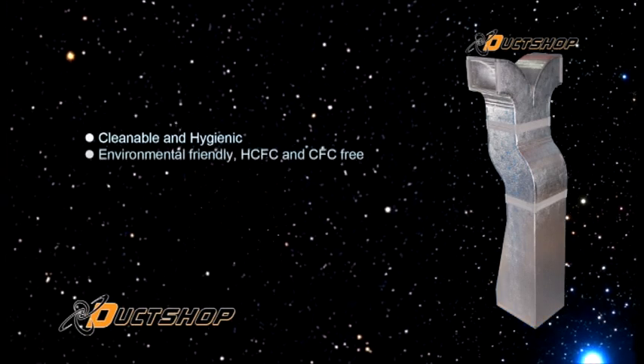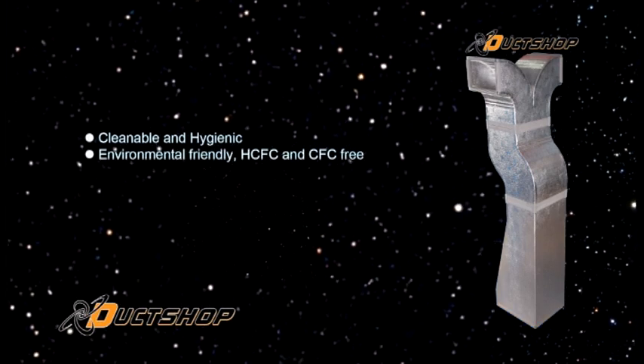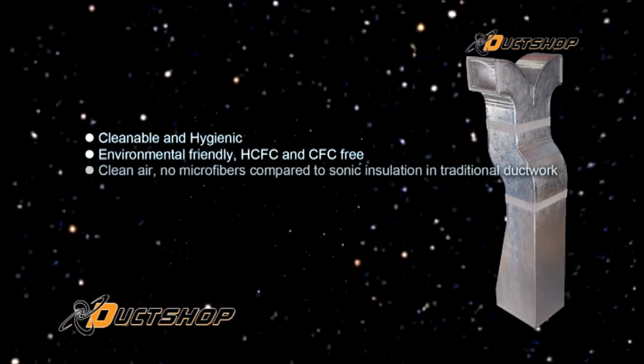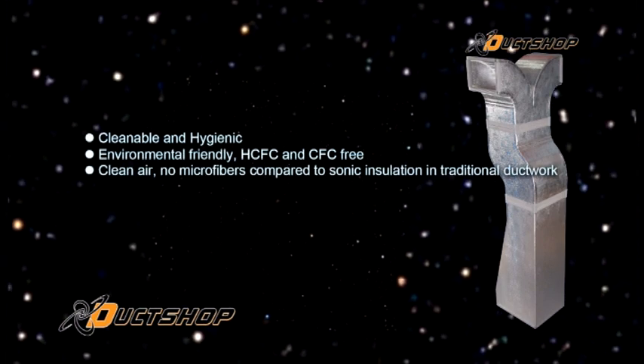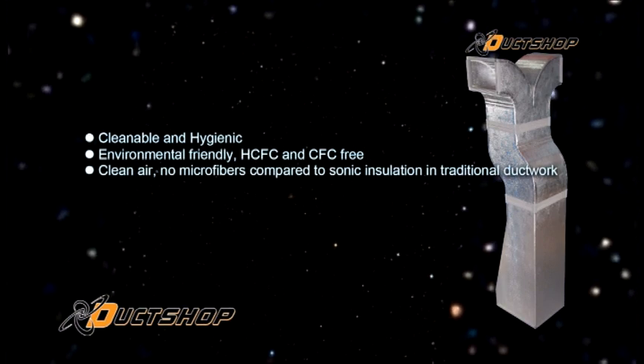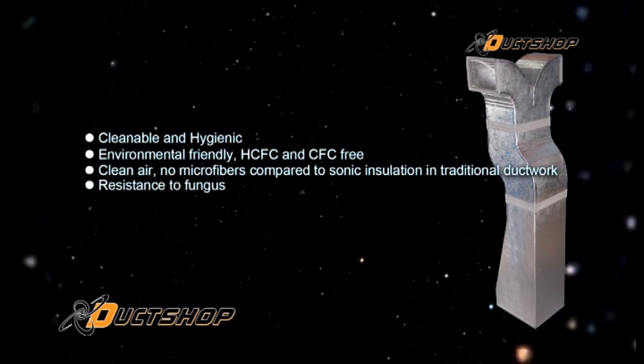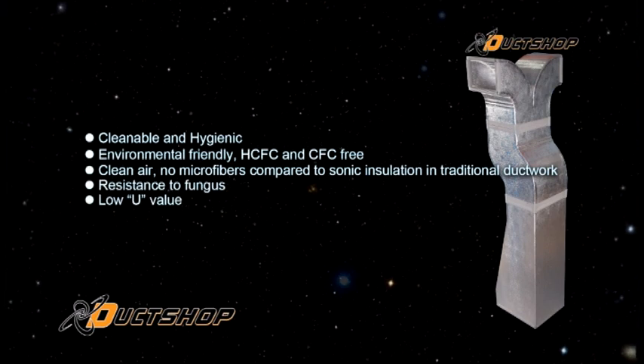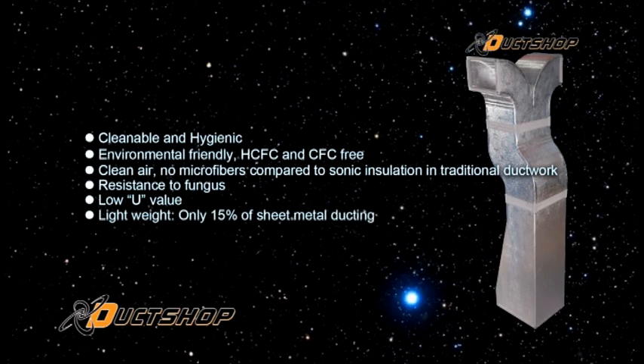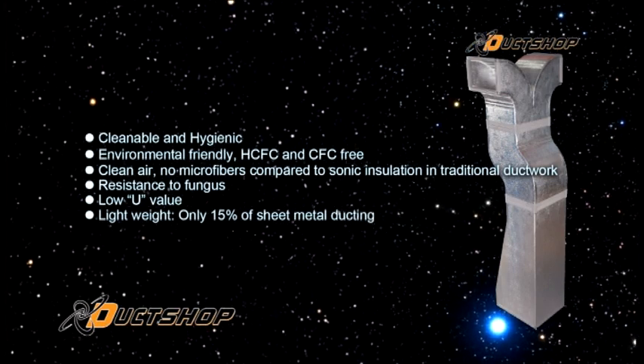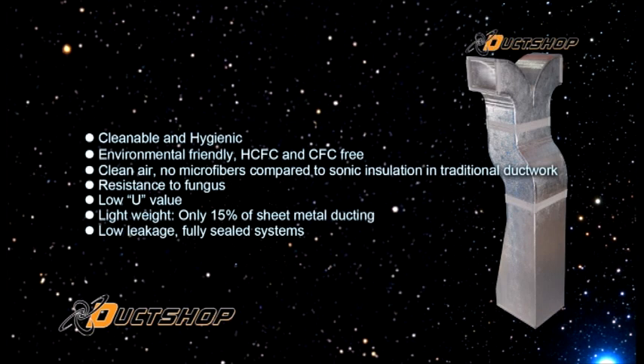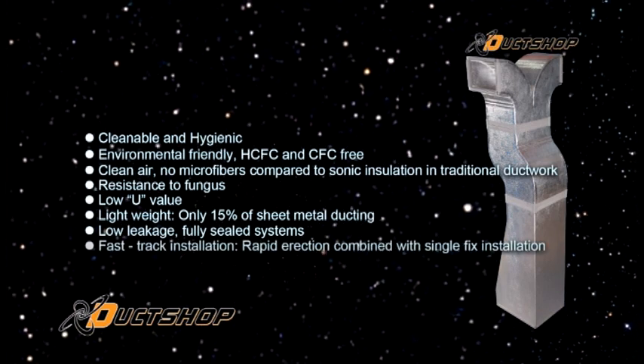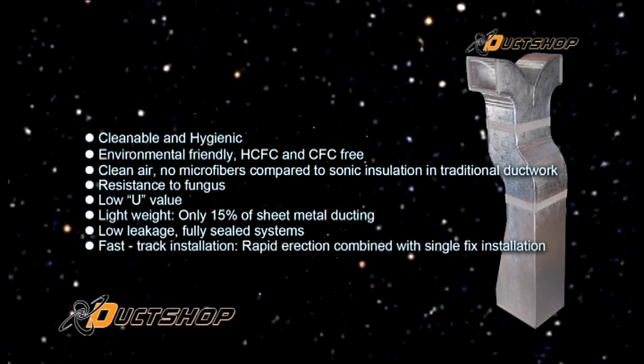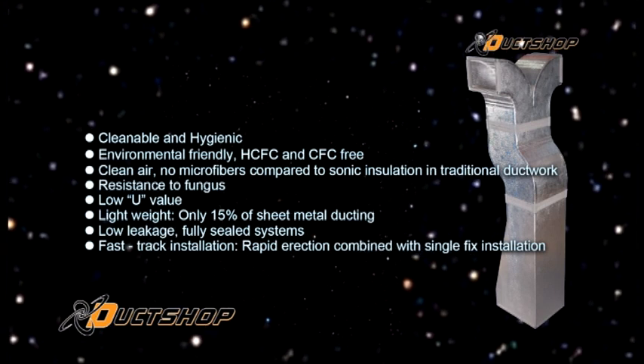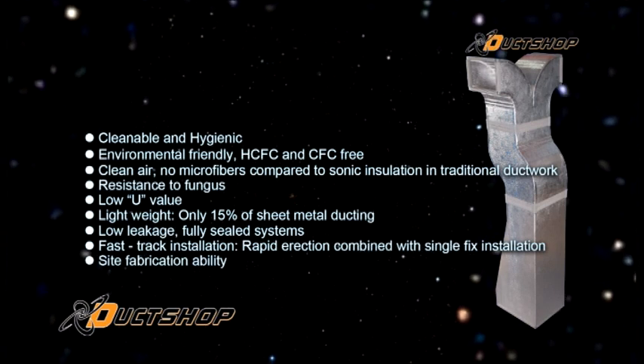Advantages: cleanable and hygienic, environmentally friendly, HCFC and CFC free, clean air, no microfibers compared to sonic insulation in traditional ductwork, resistance to fungus, low U value, lightweight, only 15% of sheet metal ducting, low leakage, fully sealed systems, fast-track installation, rapid erection combined with single fix installation, site fabrication ability.